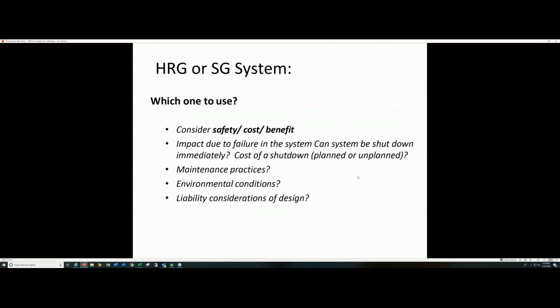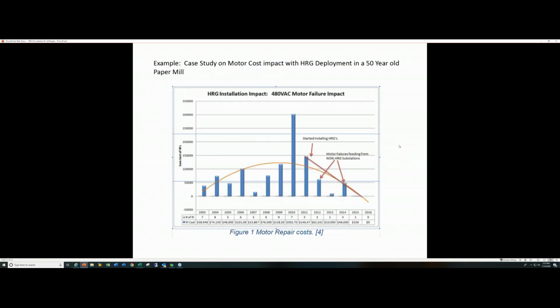So what do we use, an HRG or a solidly grounded system? Well, you need to consider your safety, your cost, and your benefit, of course. That's with everything we do. And the impact of failure to the system. Can we shut it down immediately? What's the cost of a shutdown or a planned or unplanned outage? What are your maintenance practices? Are you maintaining your equipment like you need to? Will you maintain your HRGs like you should? Do you have monitoring of your resistors like you need to? Are there any environmental conditions you need to consider where you're deploying this? And of course, as with everything we do, are there liability considerations for your particular design?